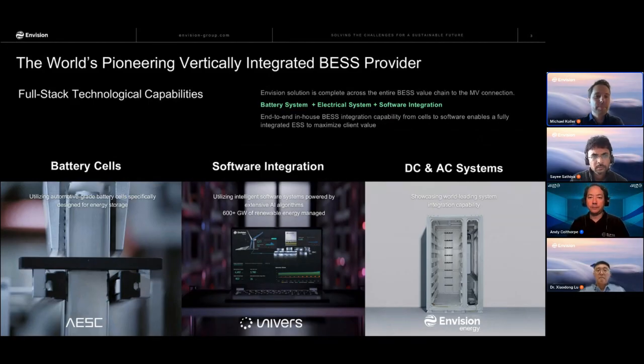And to make an example, in the context of grid forming, one of the key elements is overload capability of current to provide inertia. And we can look at this in a holistic fashion, from DC overload current on the batteries to AC overload current of the PCS. So this integrated approach from cells over software to overall hardware offers the advantage that we can look at these applications from end to end.